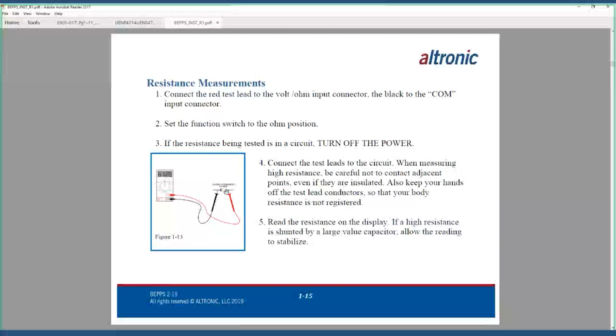So if I have a resistor installed in a circuit and a wire going from each end and landing somewhere else, I have to isolate those ends, or my test for that circuit that I'm trying to measure the resistance on is null and void, because there's too many other things that can throw it off and cause me to get a false reading. Connect the test leads to the circuit. When measuring high resistance, be careful not to contact adjacent points even if they are insulated. Also, keep your hands off the test lead conductor so that your body resistance is not registered.